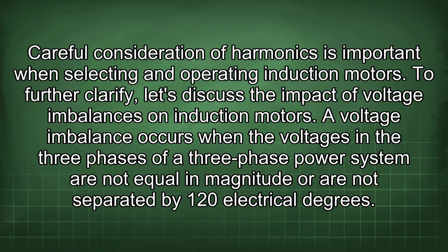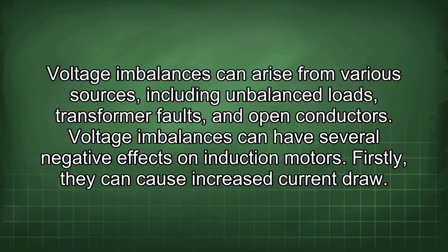To further clarify, let's discuss the impact of voltage imbalances on induction motors. A voltage imbalance occurs when the voltages in the three phases of a three-phase power system are not equal in magnitude or are not separated by 120 electrical degrees. Voltage imbalances can arise from various sources, including unbalanced loads, transformer faults, and open conductors.